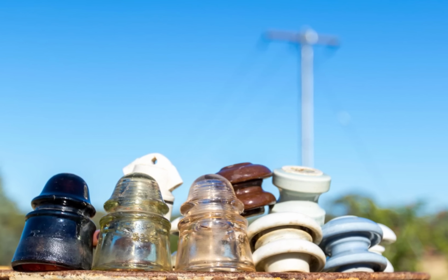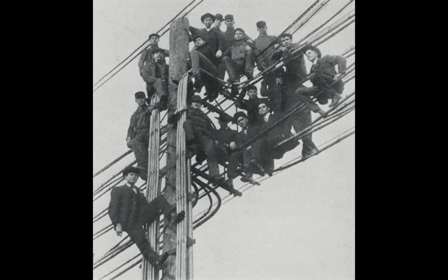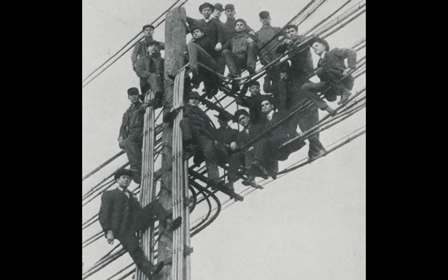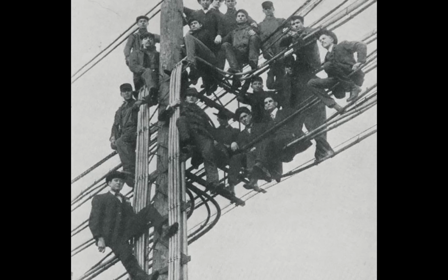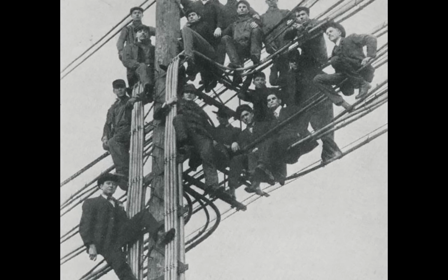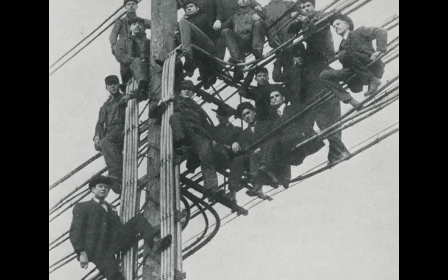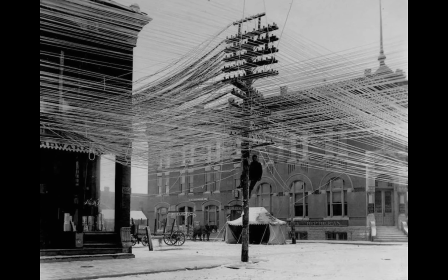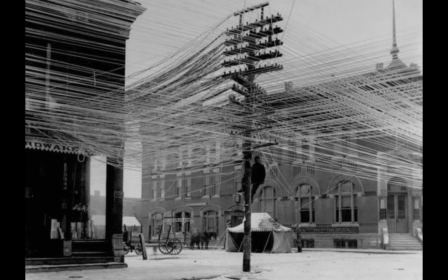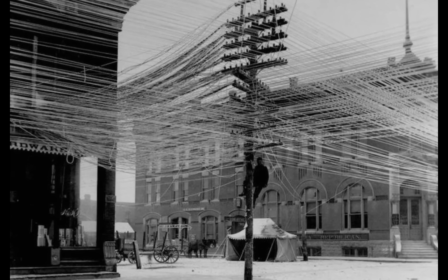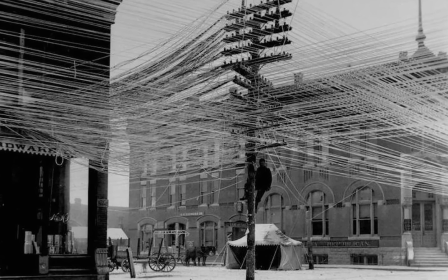But every inch you add to the insulator also adds leverage. The insulator isn't just resisting electrical stress anymore. It's resisting the mechanical stress of wind, ice, and the sheer weight of the wire, all transmitted through a single rigid pin. By the time voltages climbed towards 60,000 and 70,000 volts in the early 1900s, the math stopped working.